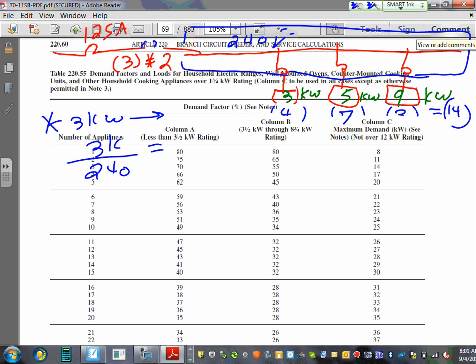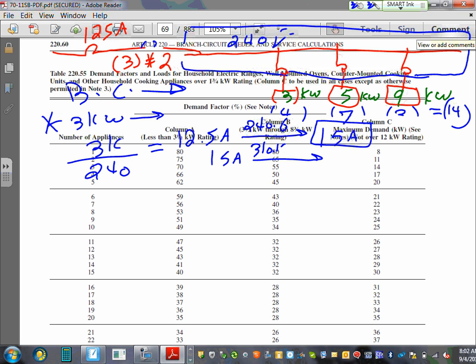Now I'm sizing branch circuits. At 12.5 amp, right? 12.5 amp. Okay, so what you're going to do is go to 240.6. What's the next standard overcurrent protection device for 12.5? 15 amps. Okay, and for 15 amp, guys, what's the conductor from 310.15(B)(16)? You need how many conductors? 3 conductors. Number? Anybody? 14 AWG. Done.